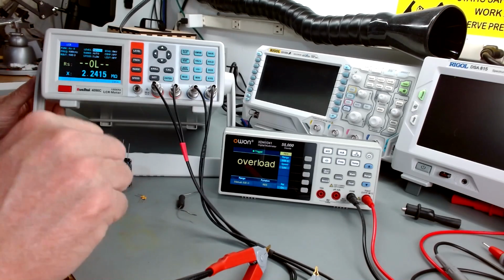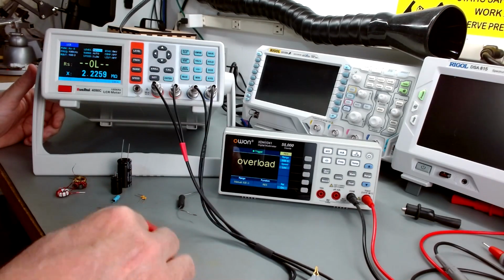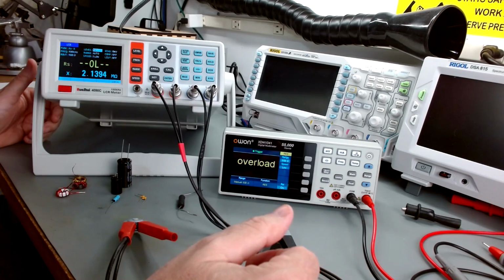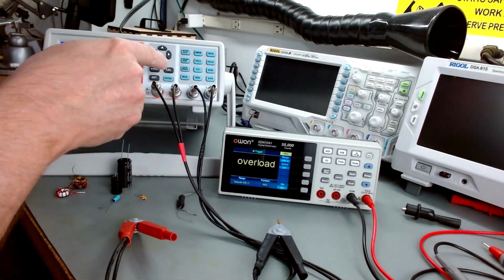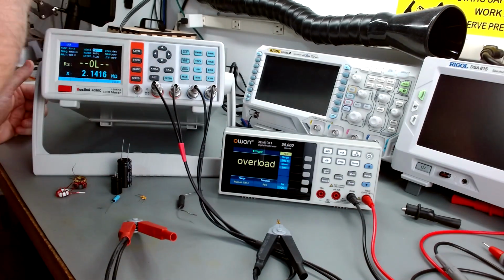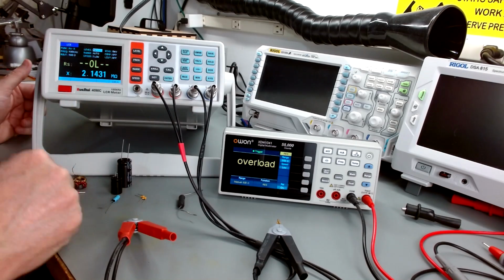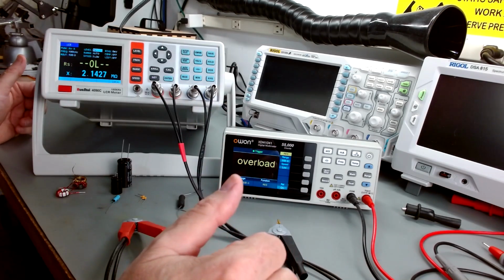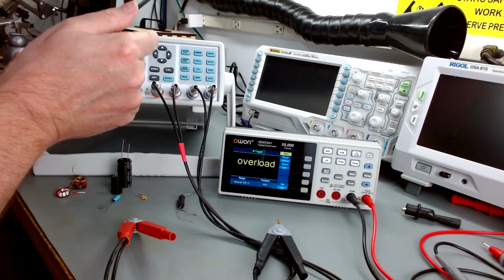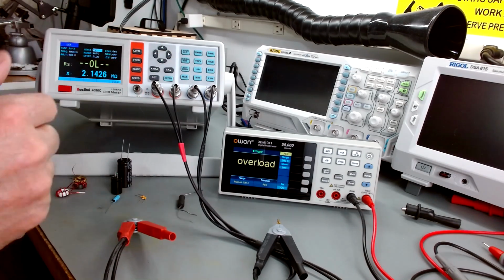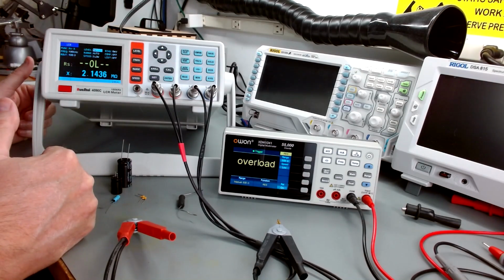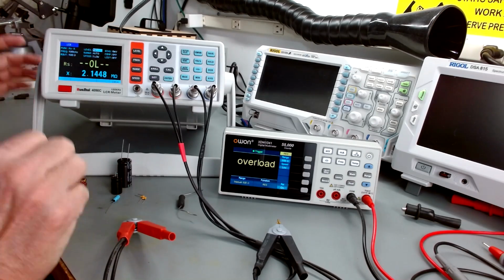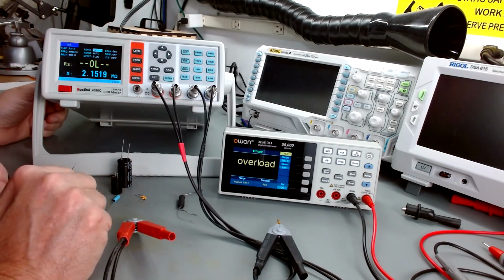Calibration is simple. You leave the probes, the Kelvin clips, open. Hold calibration for a few seconds and it'll run through and do an open. It recognizes they're disconnected. You short them, you do the same thing. It recognizes that they're shorted and it'll run a shorted calibration, and then you're good to go. So it's not hard to do, it just takes a couple minutes.